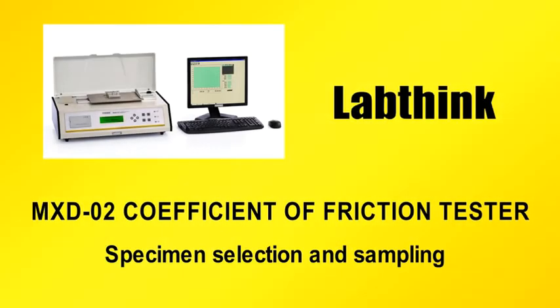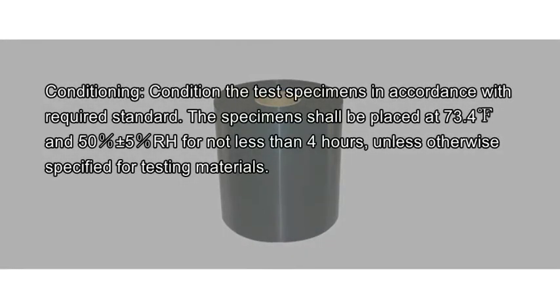Specimen Selection and Sampling. Conditioning: condition the test specimens in accordance with the required standard. The specimen shall be placed at 23±2°C (73.4±3.6°F) and 50±5% relative humidity for no less than 4 hours, unless otherwise specified for the testing materials.